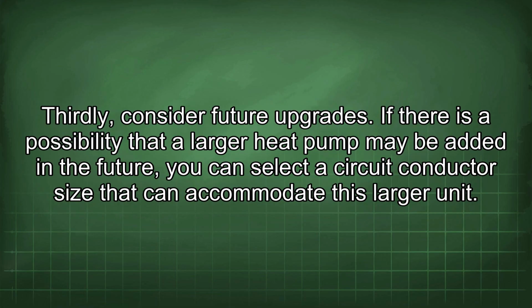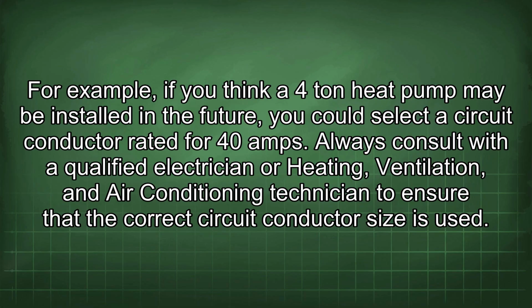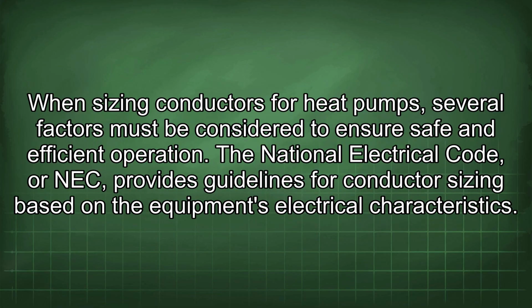Thirdly, consider future upgrades. If there is a possibility that a larger heat pump may be added in the future, you can select a circuit conductor size that can accommodate this larger unit. For example, if you think a 4-ton heat pump may be installed in the future, you could select a circuit conductor rated for 40 amps. Always consult with a qualified electrician or heating, ventilation, and air conditioning technician to ensure that the correct circuit conductor size is used. When sizing conductors for heat pumps, several factors must be considered to ensure safe and efficient operation.